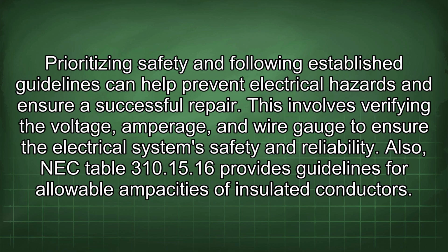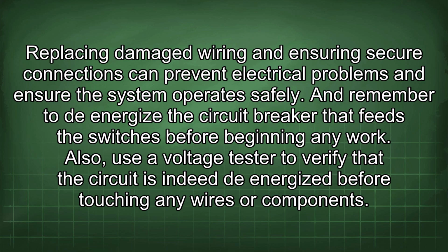This involves verifying the voltage, amperage, and wire gauge to ensure the electrical system's safety and reliability. Also, NEC Table 310.15/16 provides guidelines for allowable ampacities of insulated conductors. Replacing damaged wiring and ensuring secure connections can prevent electrical problems and ensure the system operates safely. And remember to de-energize the circuit breaker that feeds the switches before beginning any work. Also, use a voltage tester to verify that the circuit is indeed de-energized before touching any wires or components.